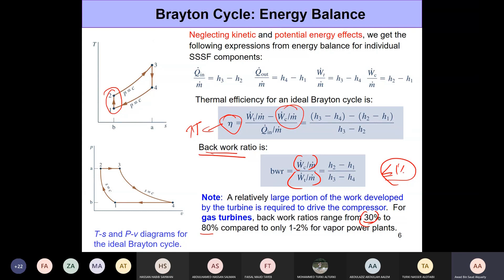But here the compressor work input is very large. It consumes a lot of work input to compress the gas from your initial pressure P1 to the final pressure P2. This is simply because of the nature of the fluid that you're compressing. It's much easier to compress liquid to a higher pressure than to compress a vapor or gas to a higher pressure. It just requires more work input, and that is what appears here in the backwork ratio. Despite the backwork ratio being so high, on the whole we are able to achieve high thermal efficiencies for a Brayton cycle simply by operating at much higher temperatures as compared to the Rankine cycle. So this is how the two cycles compare. They're very similar in a lot of aspects, but they're also different in terms of the operation range.